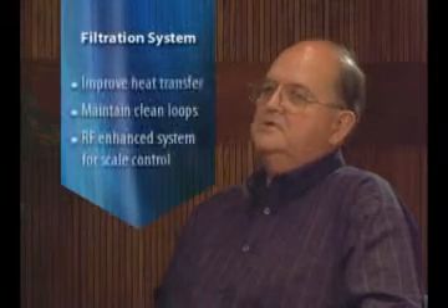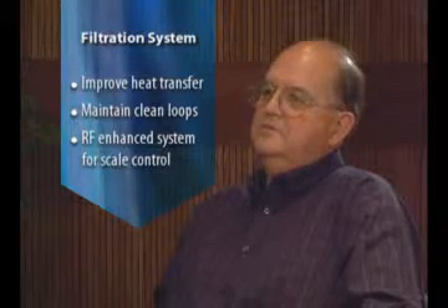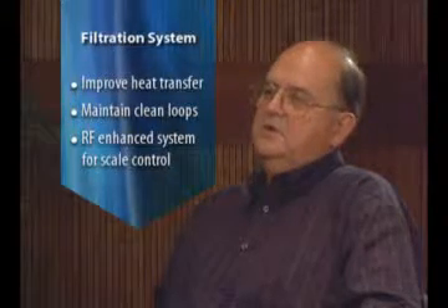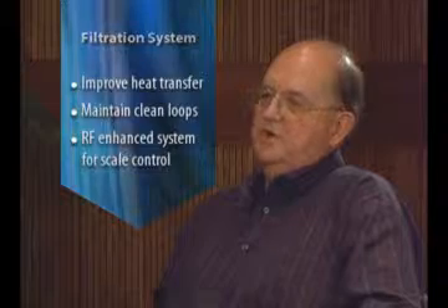After we got the condenser water side taken care of and looking good on the chiller, we started addressing the chill water problems with treatment on it, and also side stream filtration to clean up the chill water loop.